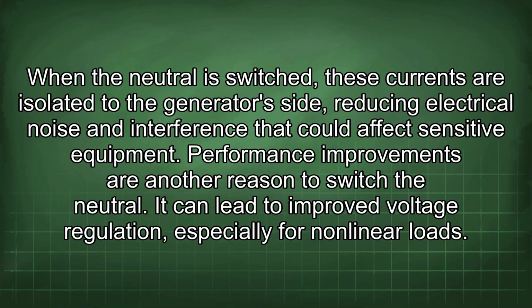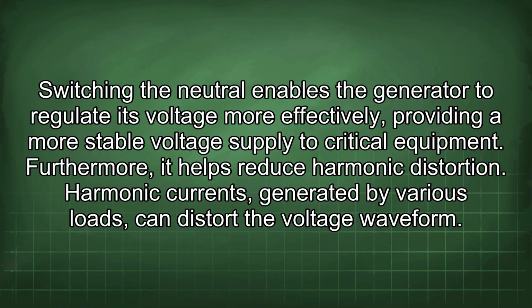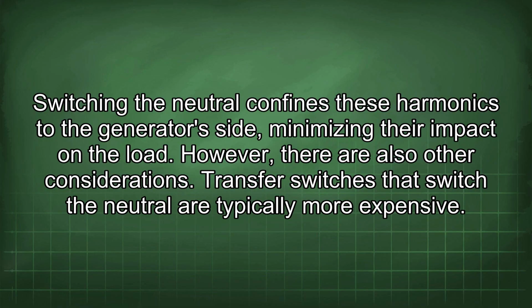It can lead to improved voltage regulation, especially for nonlinear loads. Switching the neutral enables the generator to regulate its voltage more effectively, providing a more stable voltage supply to critical equipment. Furthermore, it helps reduce harmonic distortion. Harmonic currents, generated by various loads, can distort the voltage waveform. Switching the neutral confines these harmonics to the generator's side, minimizing their impact on the load.